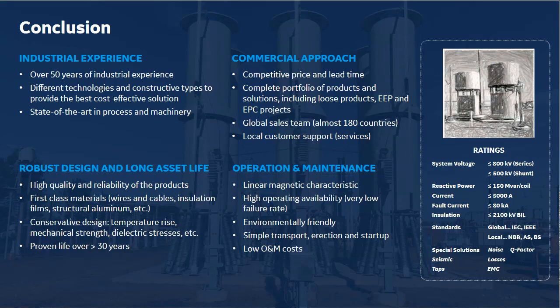So first question is, what maintenance and testing procedures are recommended to better monitor and assess how air core reactors are holding up in the field? That's actually a very good question. I mentioned maintenance-free design. One characteristic of the oil-filled technology is that you can measure and monitor the gas contamination of the tank. For an air core dry type design, there is no oil, there is no gas control. So basically, it's difficult to predict and see how good the reactors are holding up at field. But there is a way to do it.